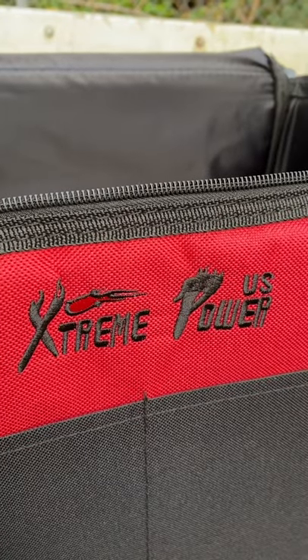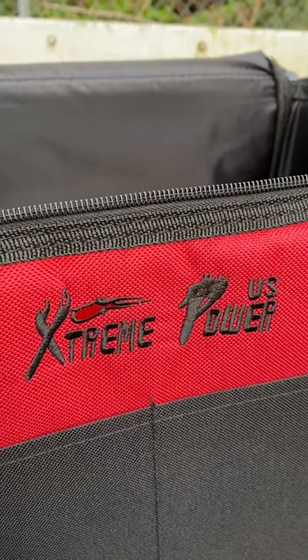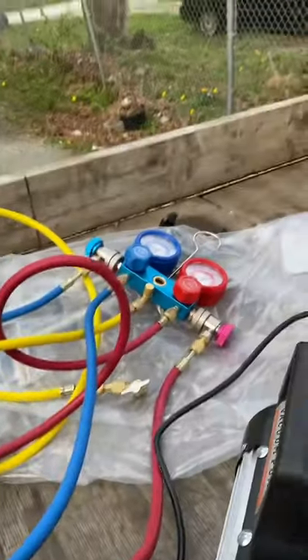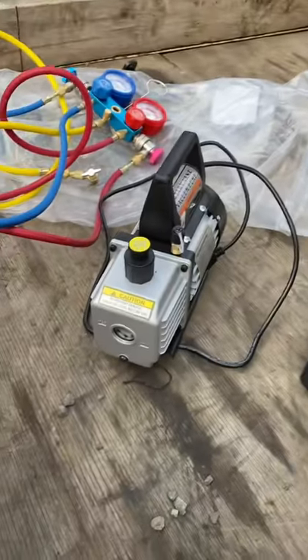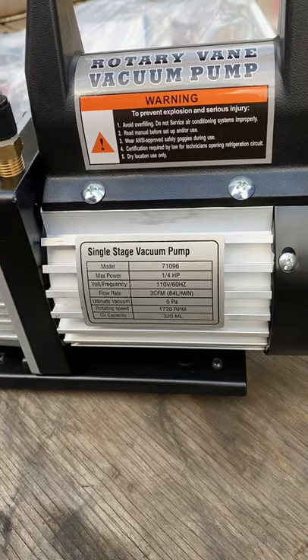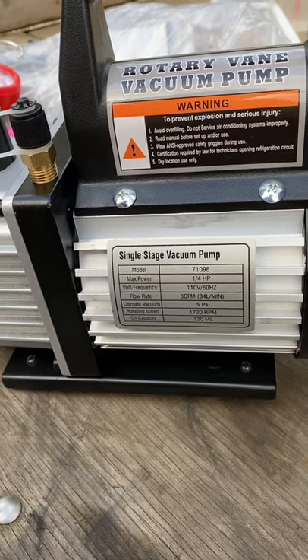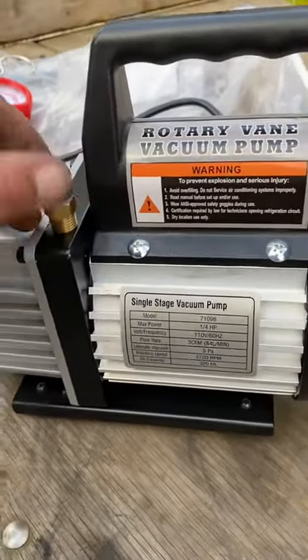Xtreme Power US — I bought this AC manifold kit. It comes with a vacuum pump. Quality-wise, it looks cheap, but maybe on par with Harbor Freight. The pump is three cubic feet per minute, 110 volts. I pulled 30 inches of vacuum immediately and it worked fine. It didn't generate a whole lot of heat. It comes with the oil — filled it up — worked fine.